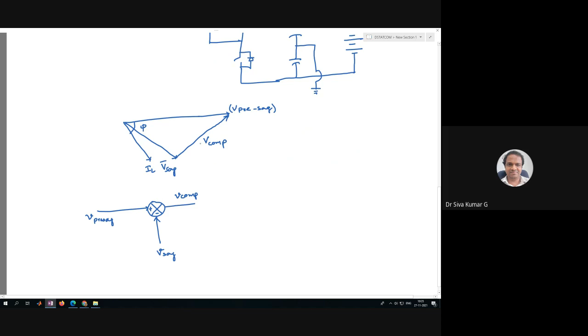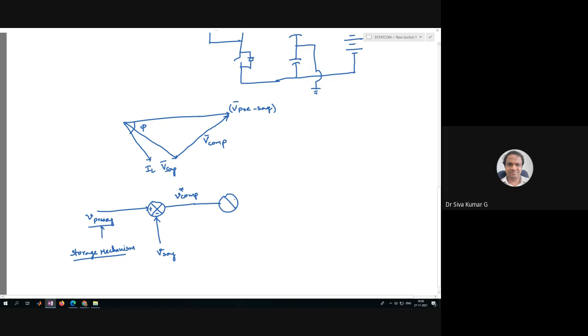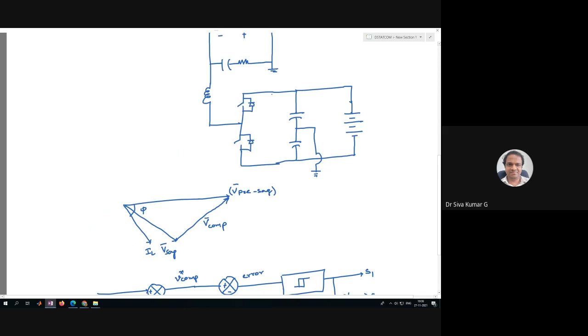What we require is a storage mechanism where we should have the pre-sag voltage also. Pre-sag voltage equation we require. Otherwise, we cannot. So once you do that, we get a compensator voltage, V compensator, and then you can have a block over here and measure this actual compensator voltage. We get an error. That error can be given to the hysteresis block. From there, we get a switching logic. Maybe we can give S1 and then the NOT gate to this S2. This is S1 and then S2.